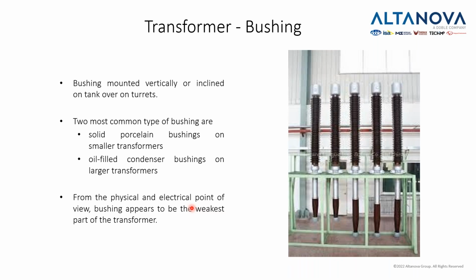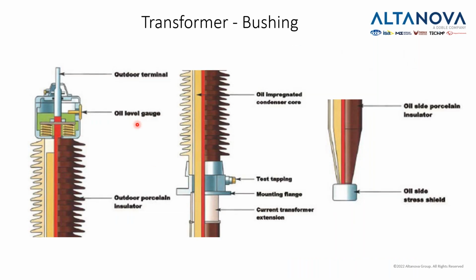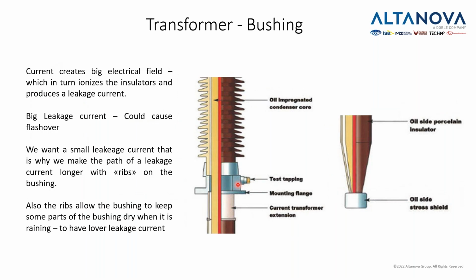Now here are some examples of bushings. They can be made from porcelain or silicone. There are all kinds of bushings, and you can see some important aspects of a bushing. One important aspect is this test tapping, or test adapter, or tap adapter. This will be used for some of the tests which we will be describing later. This is at the bottom of your bushing. Now, just to let you know, if somebody was curious why these look like little mushrooms or ribs, they look like this basically to reduce the leakage current, and also, when it's raining, to keep one part dry. If the rain is falling from this direction, the part below will be dry, which will definitely reduce the leakage current.